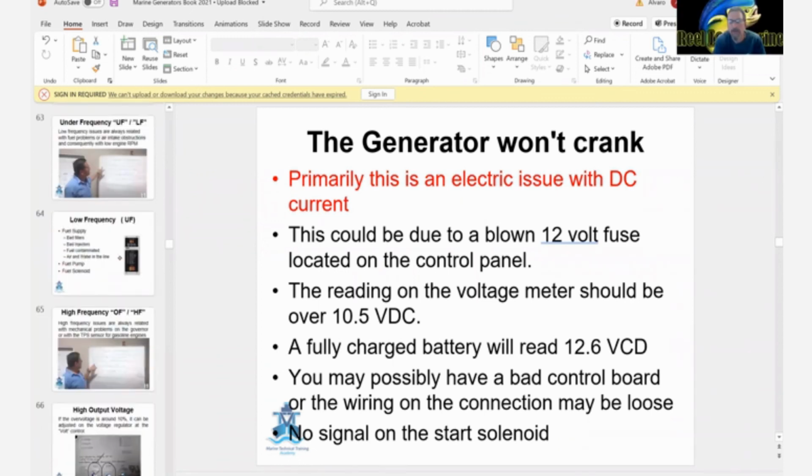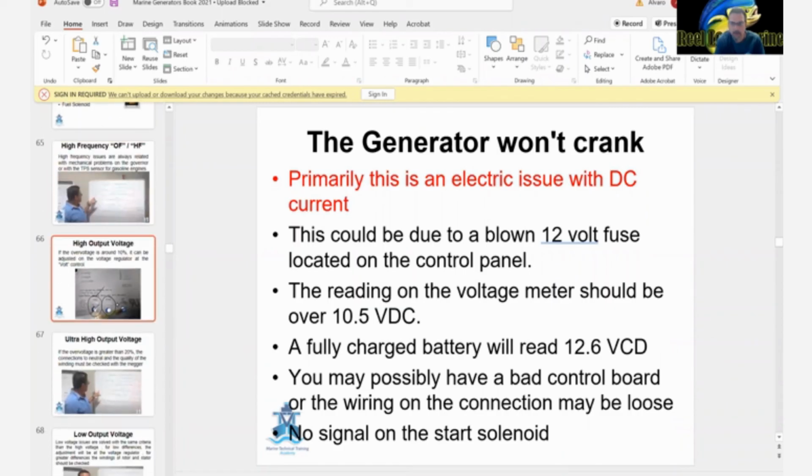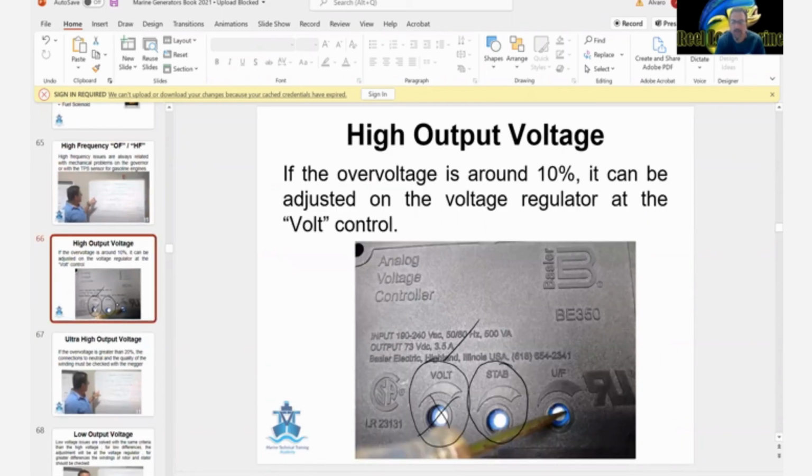So the voltage adjustment would be the one that would damage the voltage regulator. Everything else will not damage the unit. Yeah, the other one, no damage. It only affects the performance of the generator in idle. You hear that accelerate and decelerate constantly. But the first one can damage the voltage regulator immediately if you adjust too much, or if you try to reduce excessive output voltage with that spot.